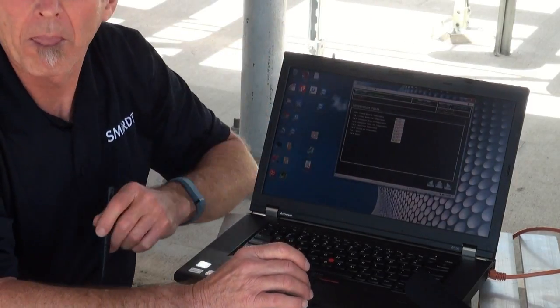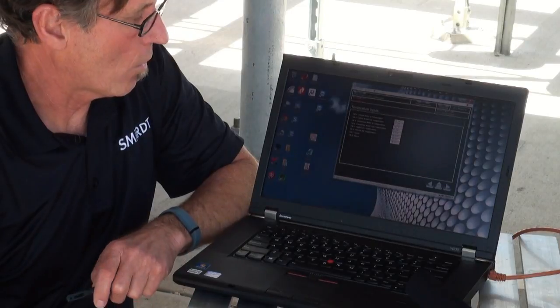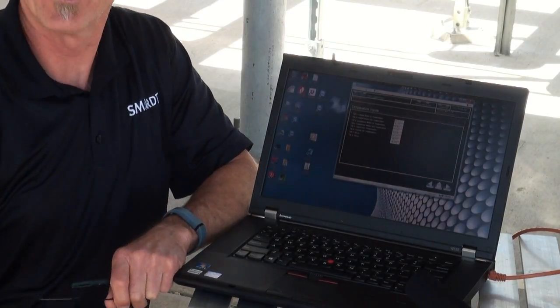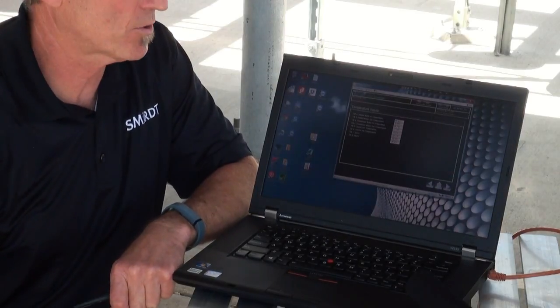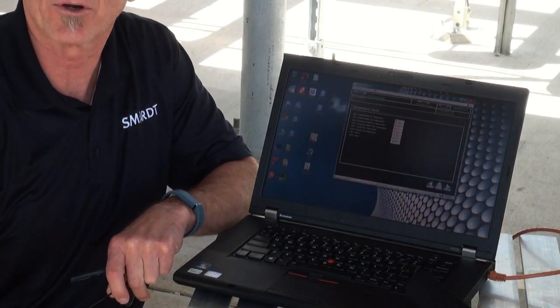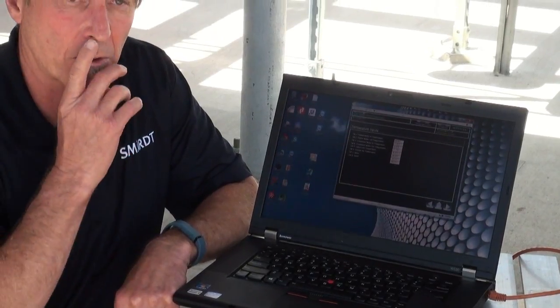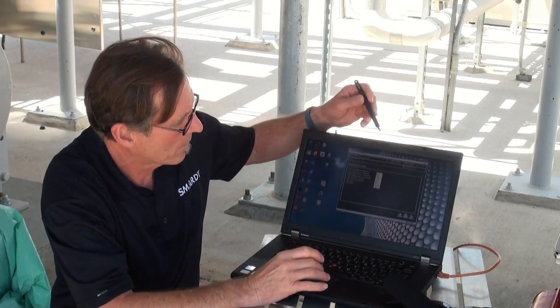Does it come up red if it goes outside of its range? No, not necessarily. But in your messages, you may get an indicator, or in your alarms, you may get an indicator, but it won't turn red. What will happen is, it's more of a service tool, but if you do a manual override of a section of the system, it will show up red. So if you do go through this and you see something in red, it's probably been overridden and should be addressed. Nothing should be overridden for any length of time.